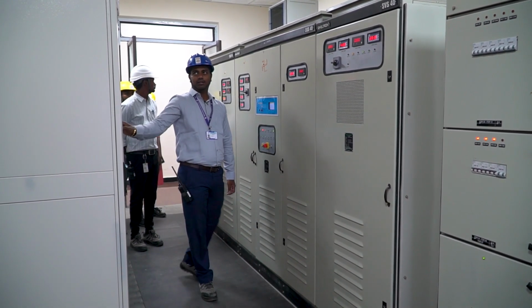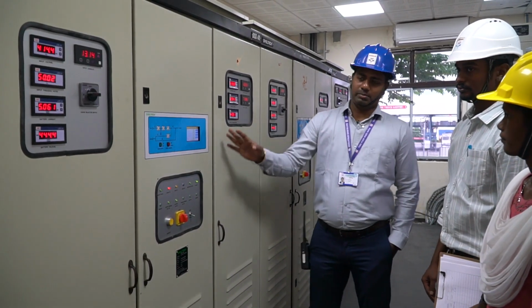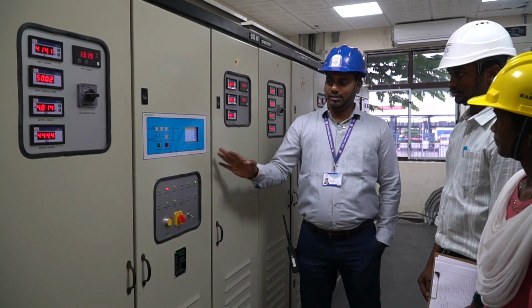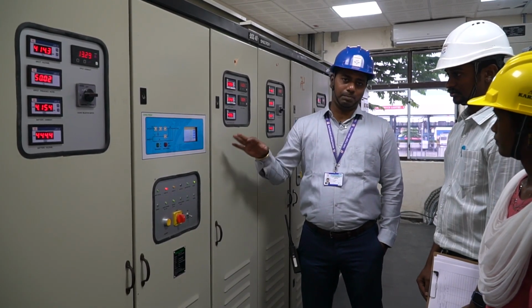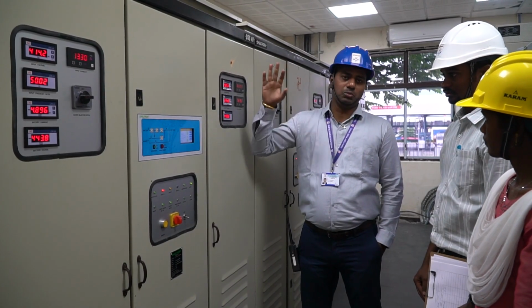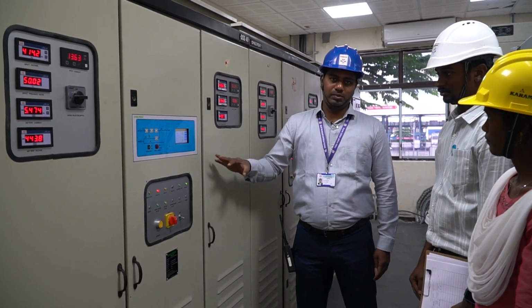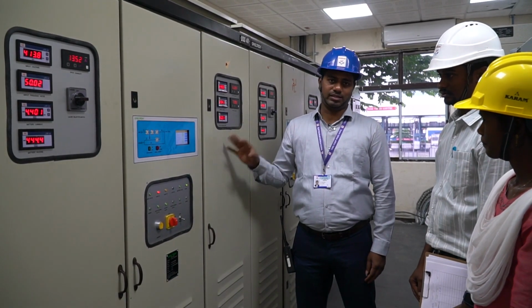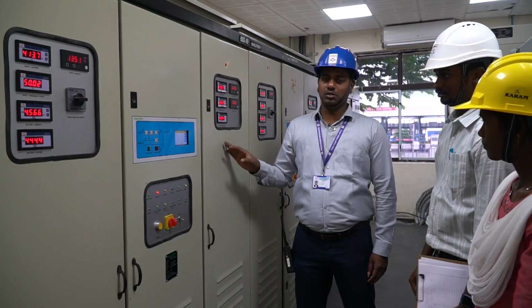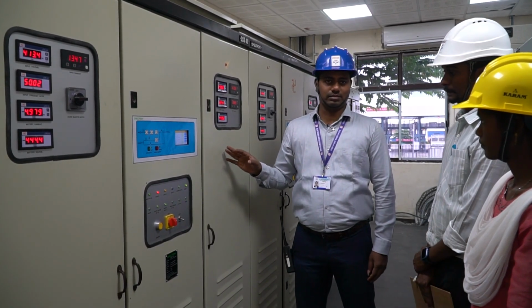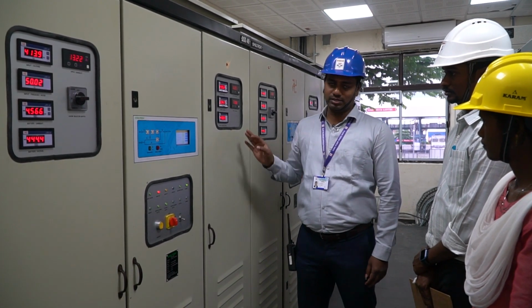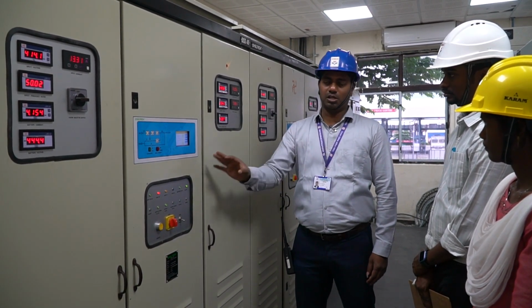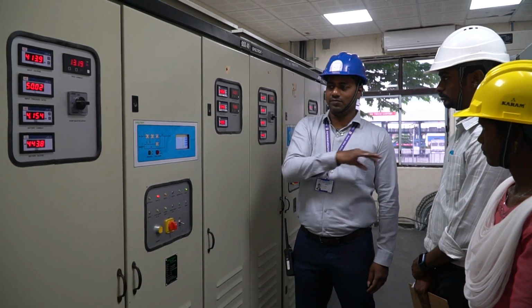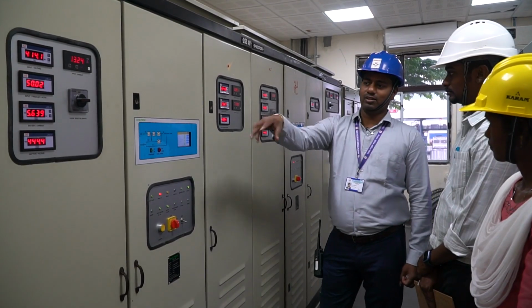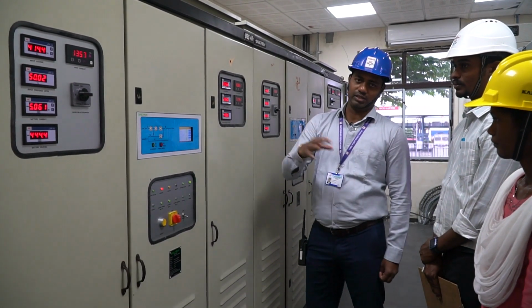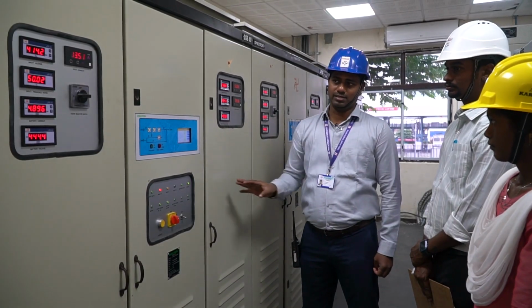On the right side we again have two UPS. One is the main UPS and another is the standby UPS, which are connected in series. This UPS will provide the minimum backup power requirement for the TAS system and the instrumentation connected with that system. So this UPS should always be alive 24/7 for our power requirement. If it goes down, the instrumentation will come down and the entire TAS system will come down. To avoid that risk, this UPS should always be in the on position, supported by the batteries. The battery's healthiness will reflect in this UPS. Now we have checked all the parameters, all are healthy. Whatever the battery's incoming and outgoing are correct and matching.